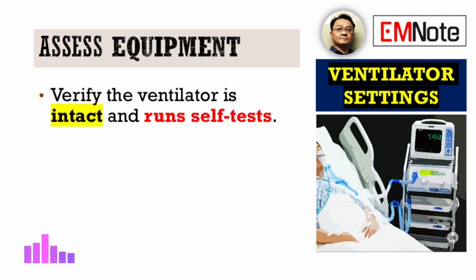First off, verify that the ventilator itself is intact and fully functional. What does that mean? It means it should successfully complete its internal self-tests, or its power-on diagnostics, without any errors popping up. These self-tests are pretty comprehensive internal system checks. They verify everything from circuit integrity to sensor calibration, alarm functions, the works.